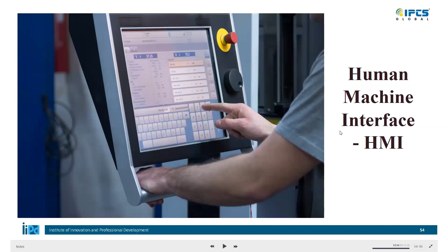Then we also have the HMI system. You can see these types of machinery everywhere, these touch screen interfaces near the machine. These are called human machine interfaces, primarily used for single machine control. When we talk about SCADA, it is multi-machine control for the whole plant, where there may be 20 or 30 different types of machinery. But the HMI package here is usually for one particular PLC or one particular machine.